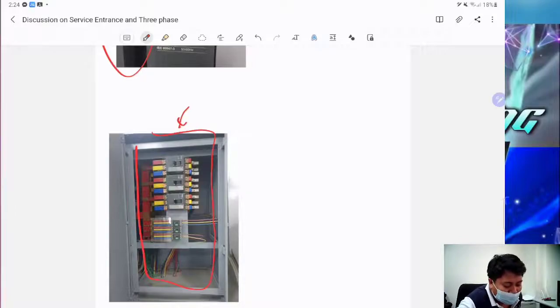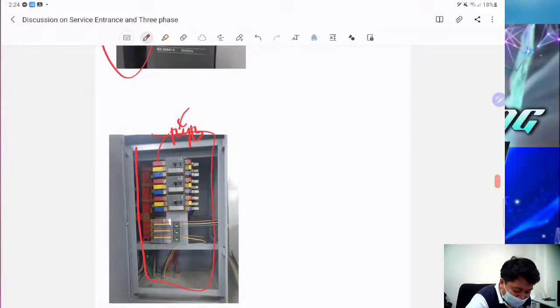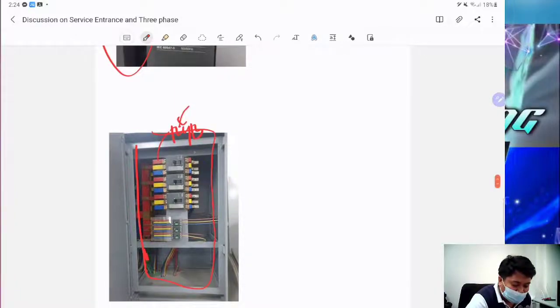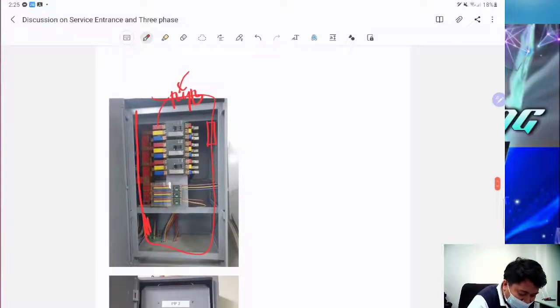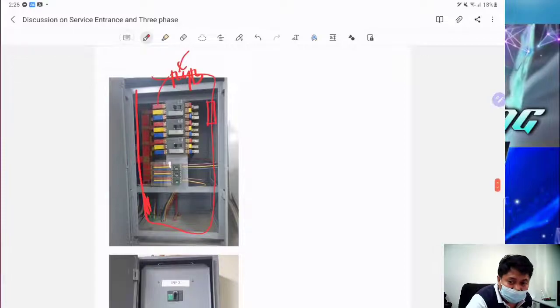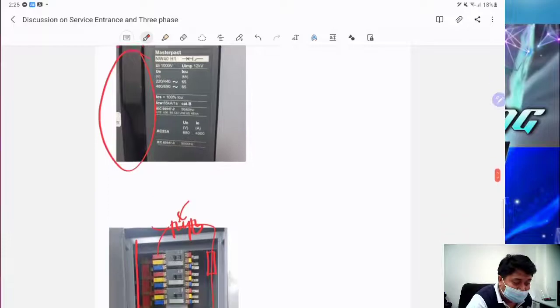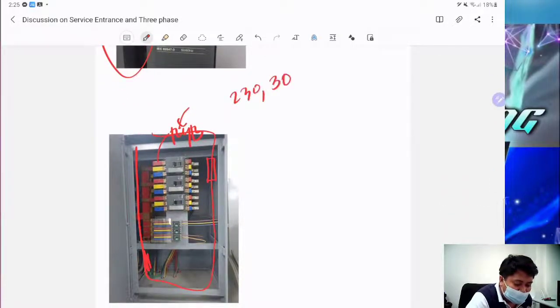So this one is the electrical panel, or the low voltage switchgear, of my sample. This is still following RYB. I will check the grounding. We have here green wires for grounding. And for the neutral conductor, that one is not there yet. So this is the grounding conductor, and based on the picture, the neutral conductor was not included. Okay, maybe the system doesn't need the neutral conductor since this is a 230 volt 3-phase. So we don't normally use a neutral conductor here.